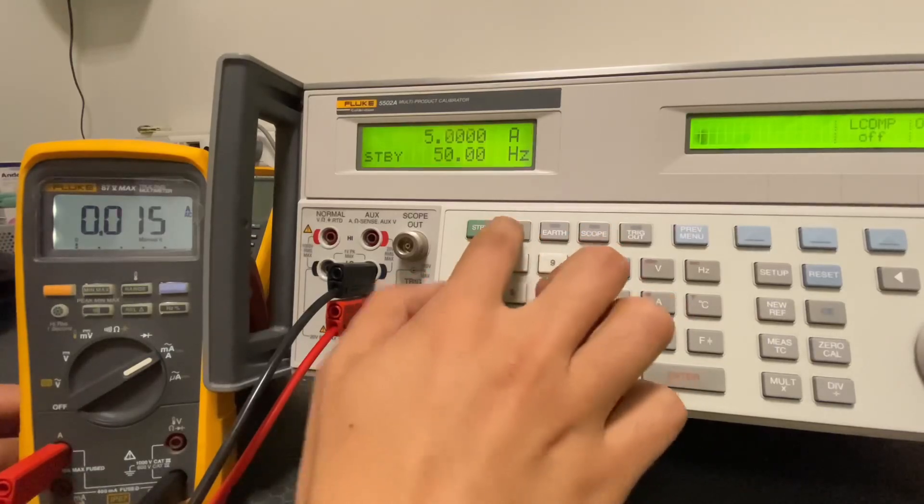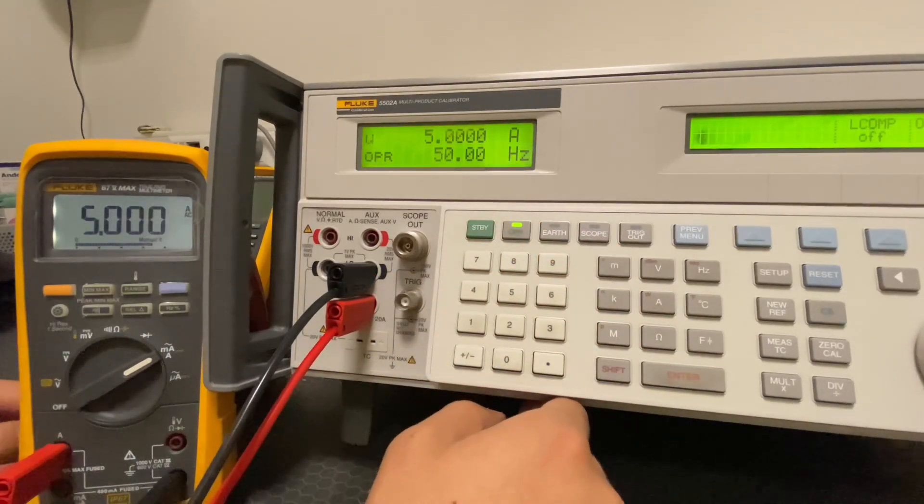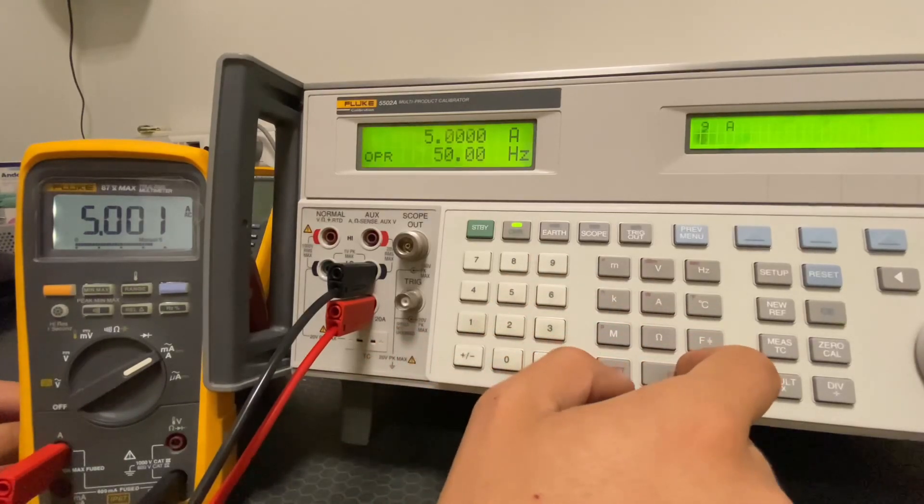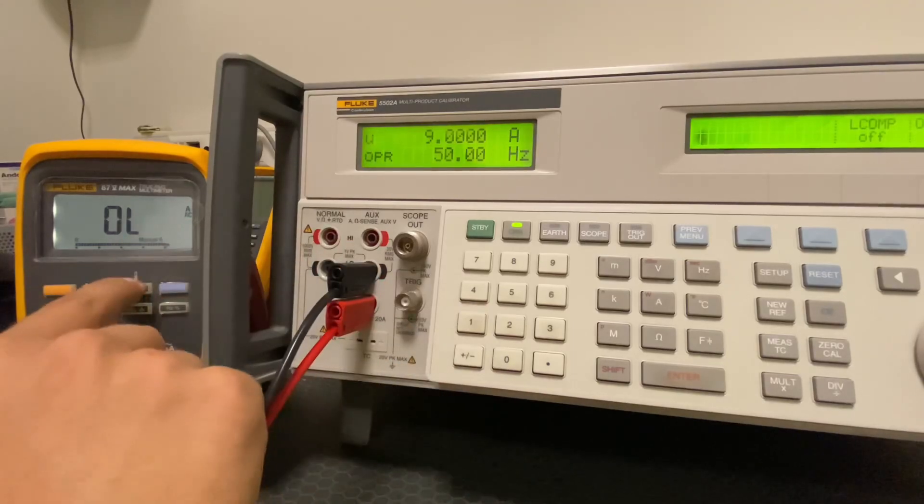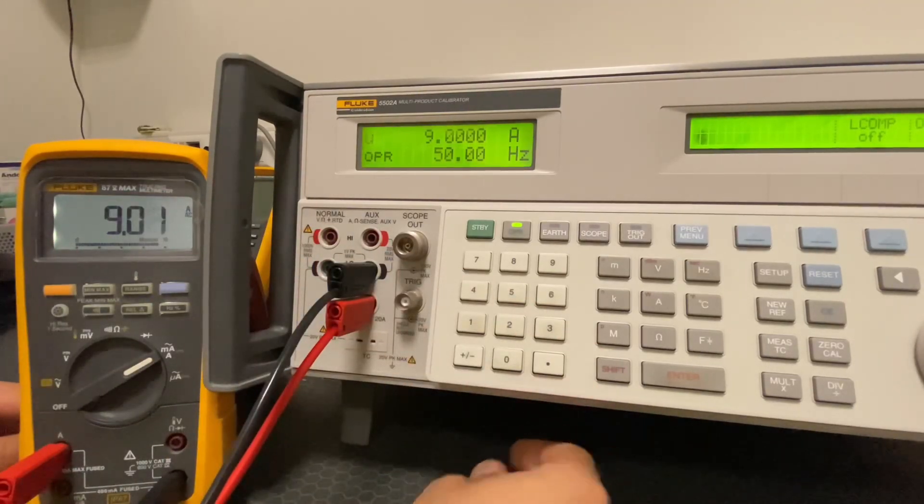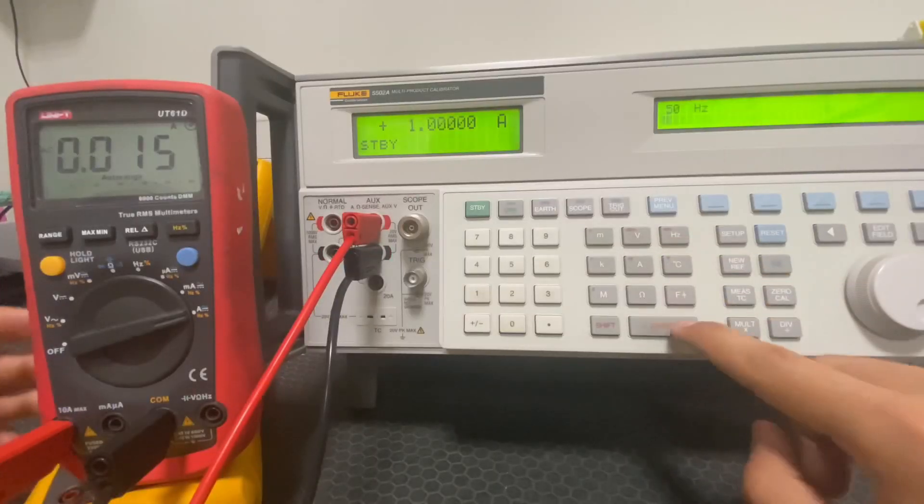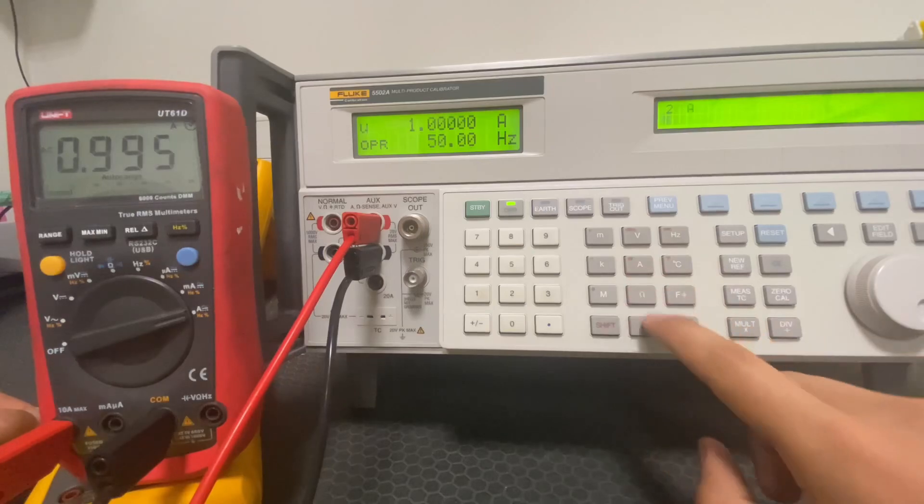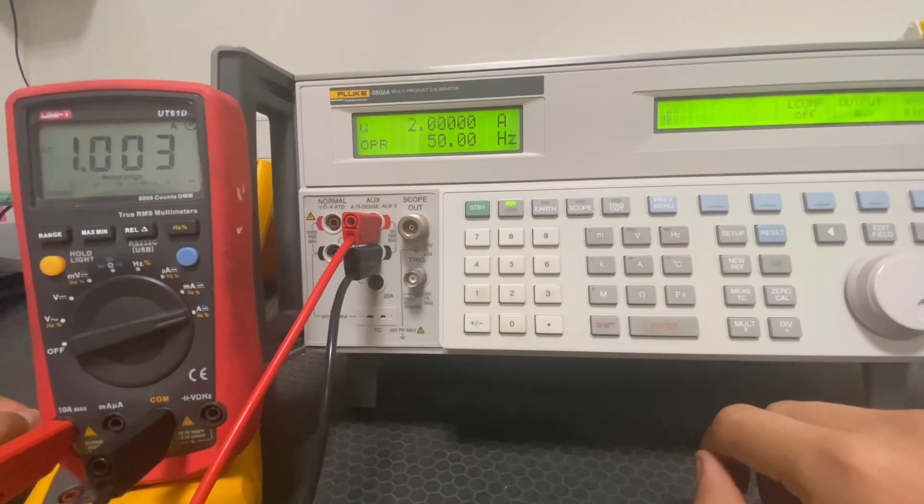The values on the Fluke multimeter appear to be quite stable. Finally, let's check 9 amps. It's giving a limit error. Let's increase the limit. We will perform the same measurements on the Uni-T multimeter and complete the comparison video. We measured 1 amp, 2 amps, 5 amps, and 9 amps.